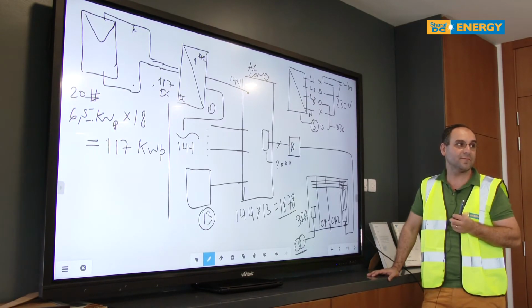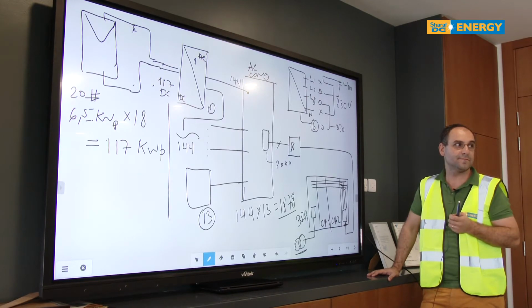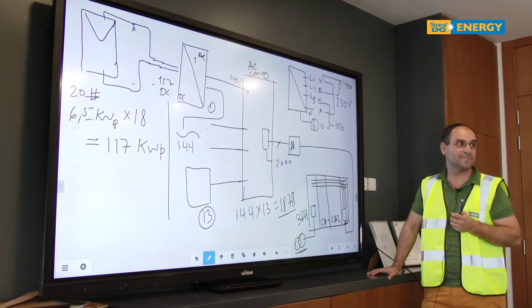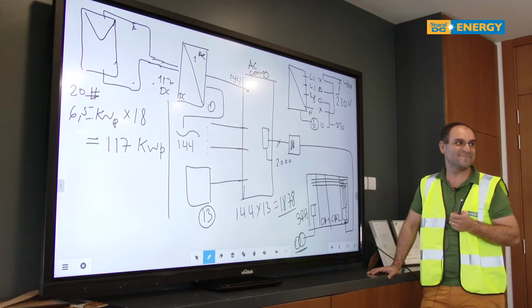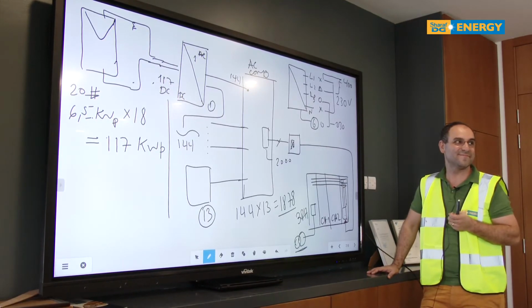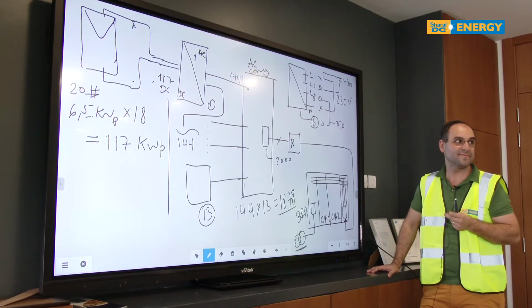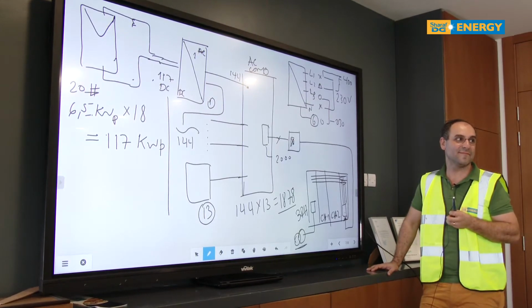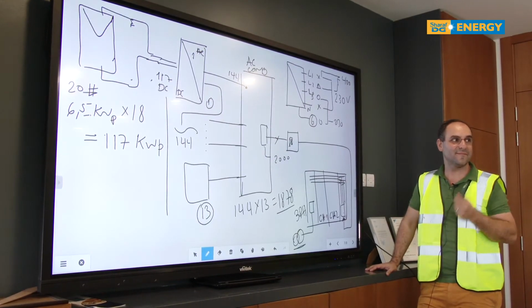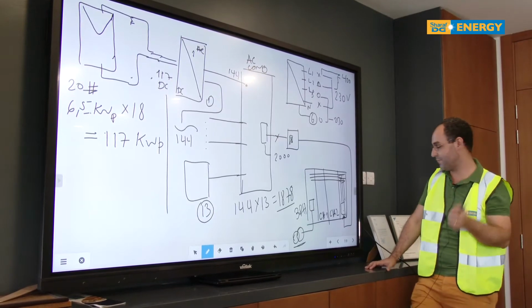If you remember, about a year back there was a fire in the Marina. These guys disconnected the supply, and then when they restored it, they didn't take care that buildings are charged stepwise. They just switched it on, and it brought a surge. Literally, one of the bus bars got burnt because of this.